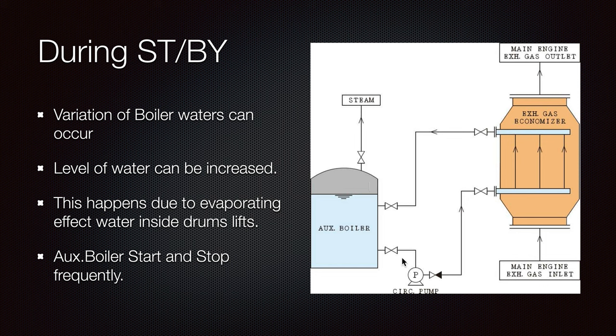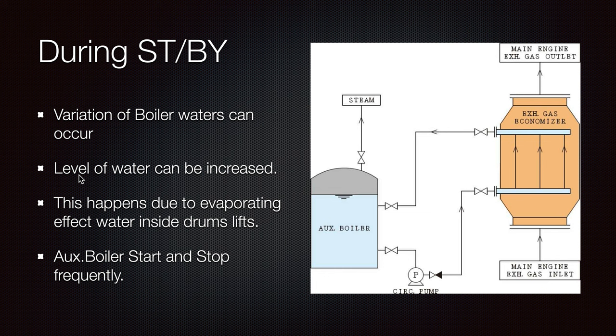In this case you can drain some of the water or leave it to adjust over time, but you won't want an alarm going off. You can drain or blow down the boiler — a blow-down is also necessary to do far away from ports, due to impurities that can be expelled into the water. The water level can increase due to the evaporation effect inside the drum.